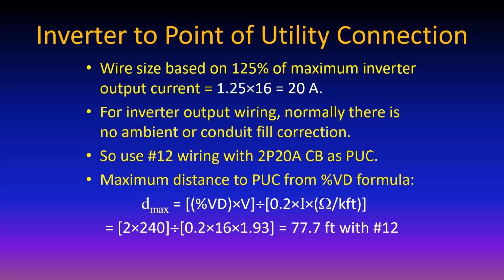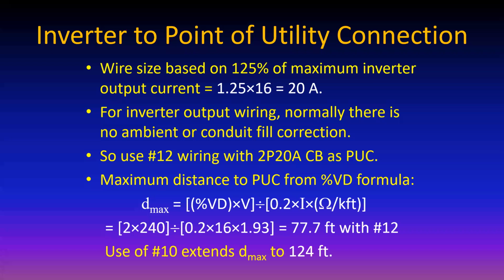And so if you're using number 12, put in the numbers, 1.93 ohms per 1,000 feet means you can go 77.7 feet between the inverter and the point of utility connection with number 12. If you put in number 10, then you can go to 124 feet.